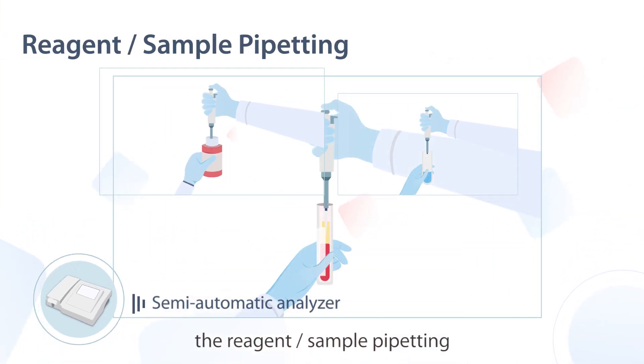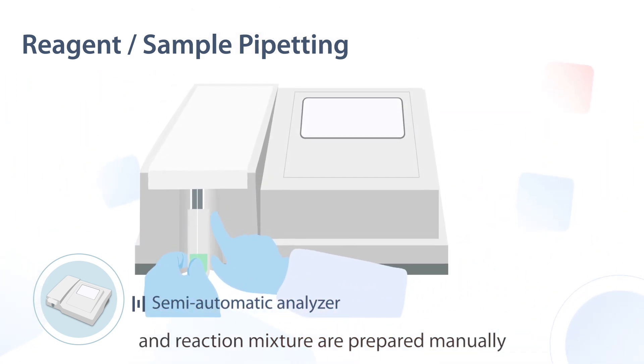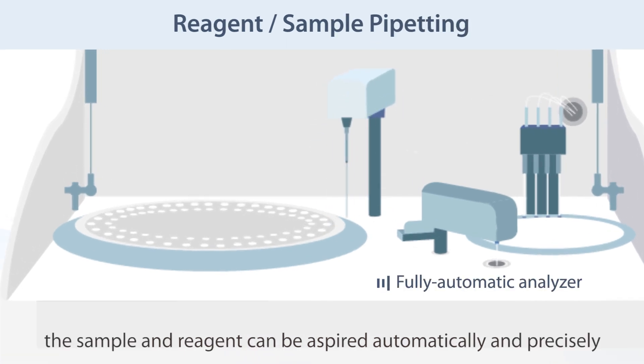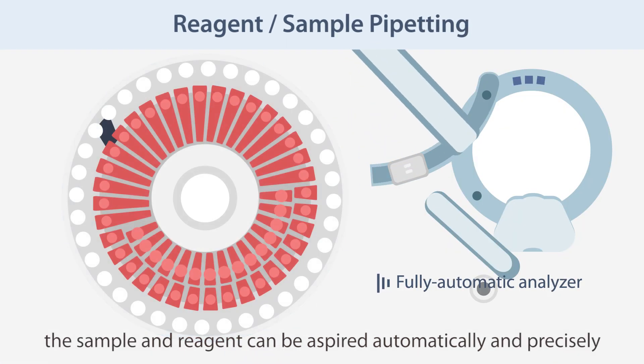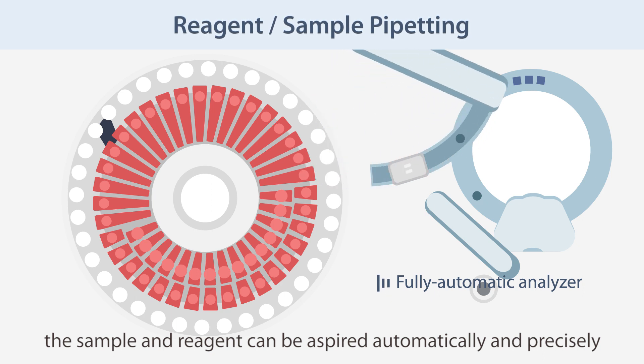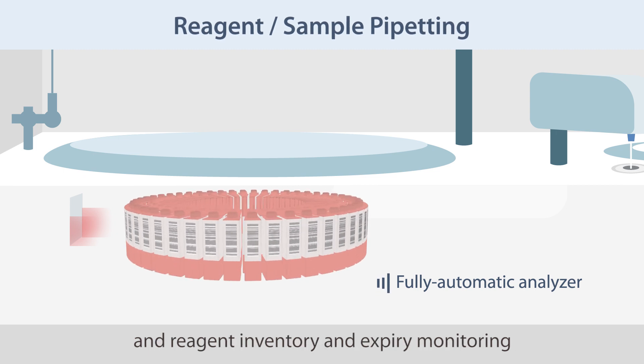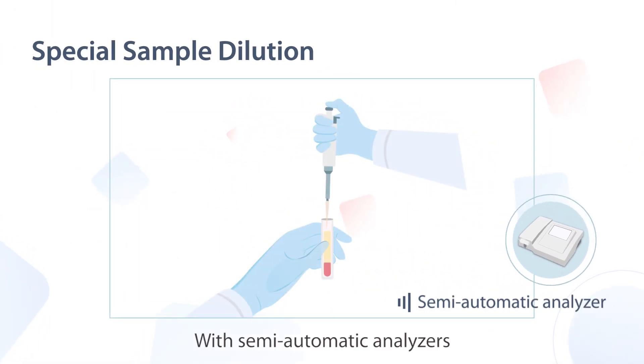In most semi-automatic analyzers, the reagent, sample pipetting, and reaction mixture are prepared manually. In an automatic chemistry analyzer, the sample and reagent can be aspirated automatically and precisely. The software can also support barcode loading and reagent inventory and expiry monitoring.